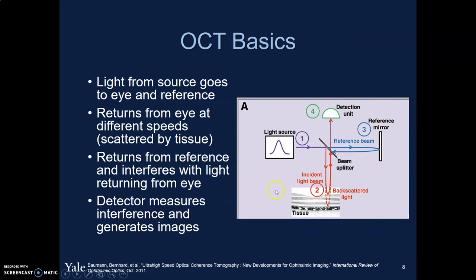So if a patient has a very dense cataract or a dense vitreous hemorrhage, we won't be able to obtain very good images. The light is generated from a light source, shot over to a splitter, which sends some light over to the tissue where it scatters and slows down through different layers. That light comes back through the detection unit. At the beam splitter level, some light is also sent to a reference arm providing a comparison, and the detection unit uses the interferences and an algorithm to generate images for us to see.